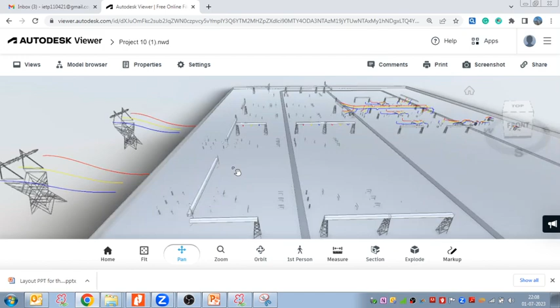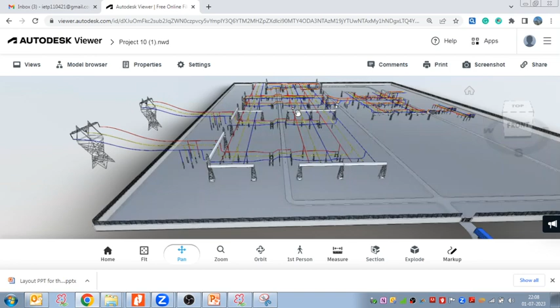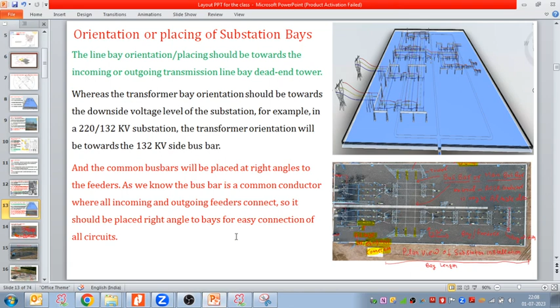So this bus bar we place at a right angle, at 90 degrees to this line bay or this transformer bay. Because this is the common conductor, it is placed at 90 degrees so that we can connect every circuit to this common conductor. For this purpose it should be placed at a 90-degree angle for easy connection of all circuits. We can see that here: we have a transformer bay, this is again a side photo, and here we have the line bay.